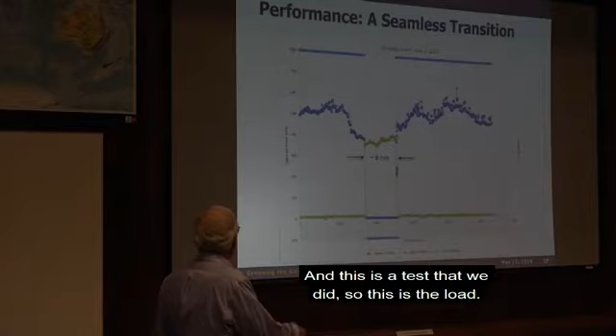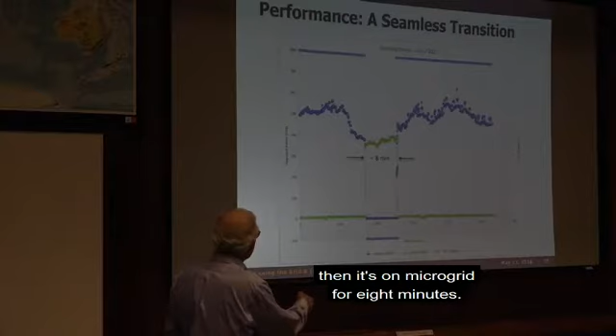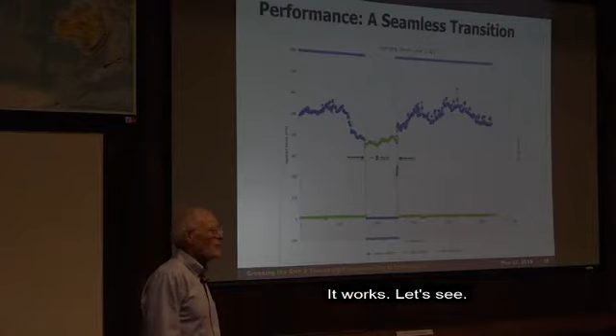This is a test we did, showing the load. The battery isn't very big, as we've said before, so we decreased the load by turning things off and locking out the elevators, since starting elevators causes a huge power surge. We got it down to a low value and then did a seamless transition: on grid power, then on microgrid for 8 minutes, then back on regular grid power. Pretty amazing—it works.